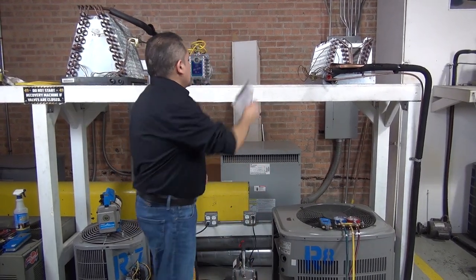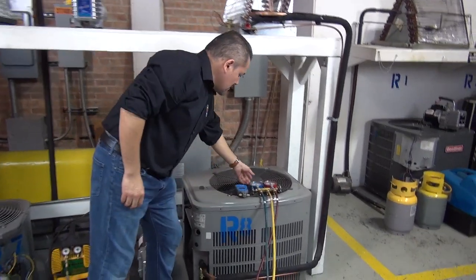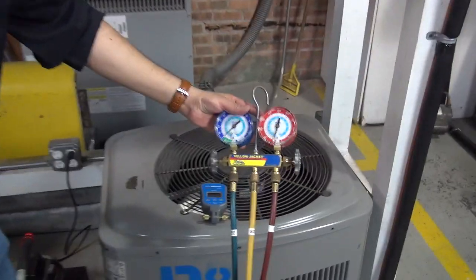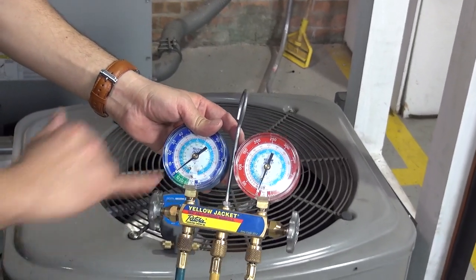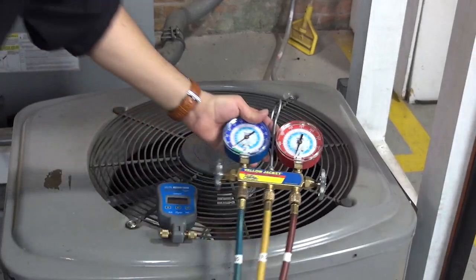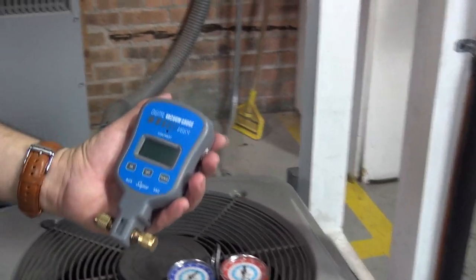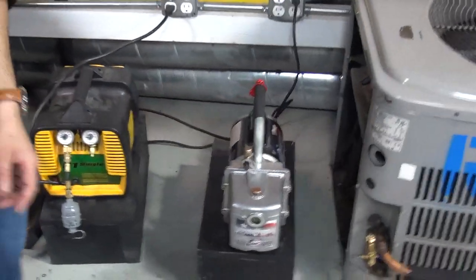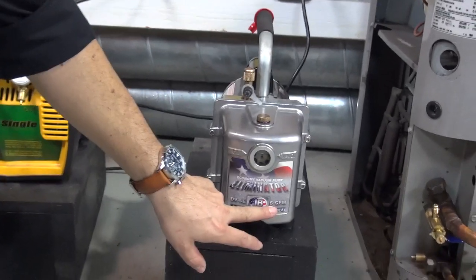We're going to cover a little bit of that information in this process. Let's start with a couple of tools. You're going to need your regular gauges — nothing special, just something that gives you positive pressure and pretty much inches of mercury or negative pressure. Don't worry too much about the high side pressure. We're also going to use a micron gauge — this one is from Supco — and we're going to be using the vacuum pump.